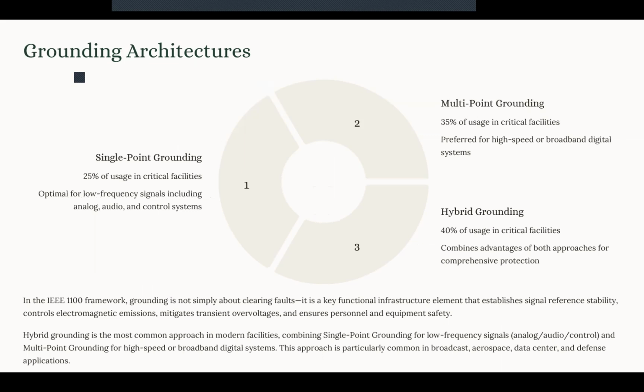Now, when we want to provide a stable low noise signal reference and at the same time maintain the fault clearing safety, we need to have a proper grounding architecture. It is important because sensitive electronic equipment is highly susceptible to common mode noise, ground loops, and high frequency transients. The chosen architecture directly affects aspects like signal integrity, EMC, and equipment reliability.